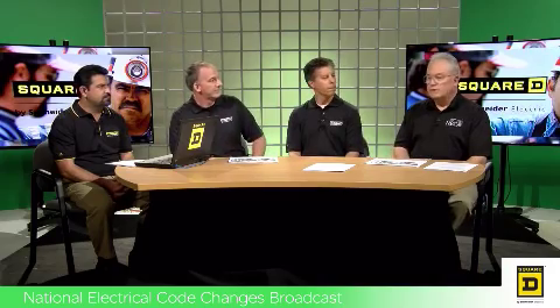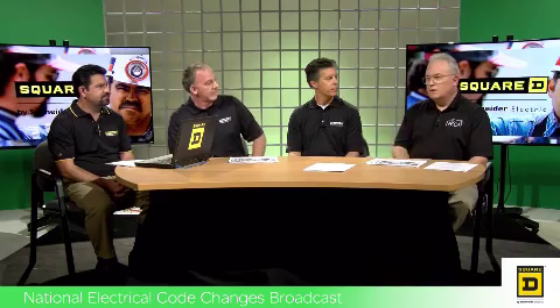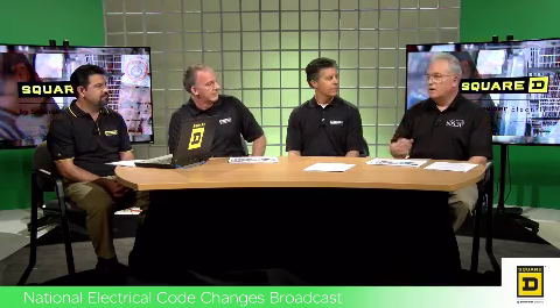That's an excellent point, Alan. You make a good point about differentiating the marking requirements in 110.24 from 110.16, and one needs to be a lot more dialed in to make sure that the incident energy and the level of PPE required to be worn for protection is accurate, whereas over in 110.24 you're dealing with values, maximum values that relate to equipment ratings and suitability for use on a system within its capability.